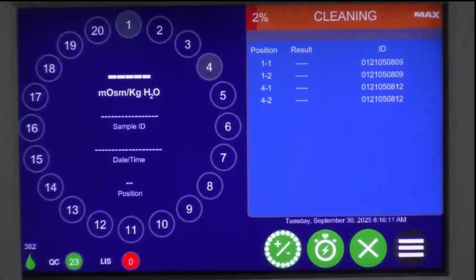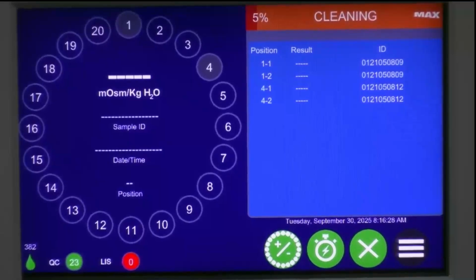our user interface here. So you're going to see the first thing that it's going to do, it's going to clean and prime the system so that it can initiate the tests, right? The most important part of these flow-through systems, just like any chemistry analyzer, is to make sure we're keeping them clean, keeping the fluidic path clear of any organic material or anything that could carry over and affect the result from one sample to the next. Super, super important.